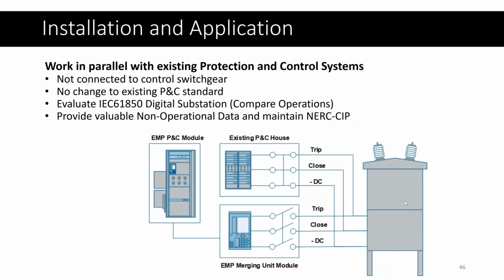So in operation, what we have is the existing protection and control package there in the top middle, in parallel with the module and the hardened control package. We leave the links open on the EMP hardened. If we were to have an EMP event, we would then close in those links and we can immediately restore the substation, put it in service. Next slide, please.